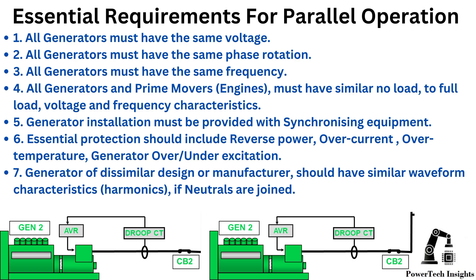5. Generator installation must be provided with synchronizing equipment. 6. Essential protections should include reverse power, over current, over temperature, generator over/under excitation. 7. Generators of dissimilar design or manufacturer should have similar waveform characteristics (harmonics) if neutrals are joined.